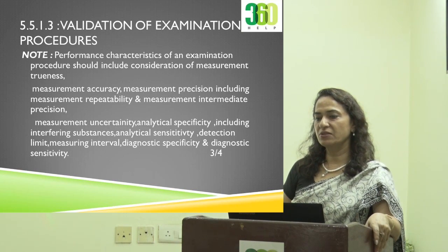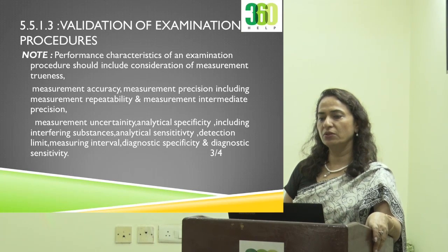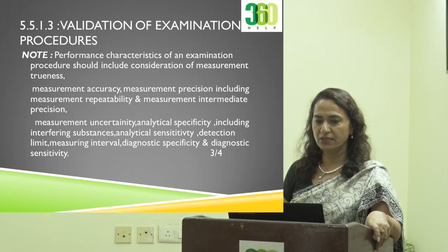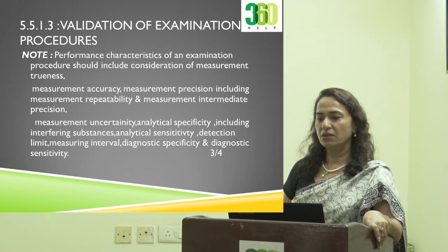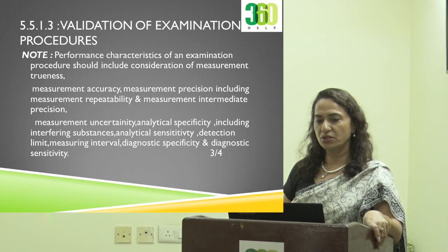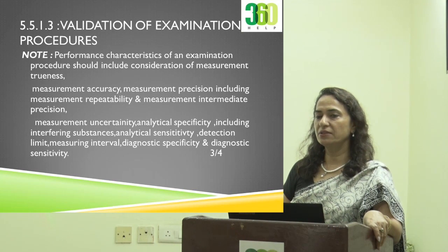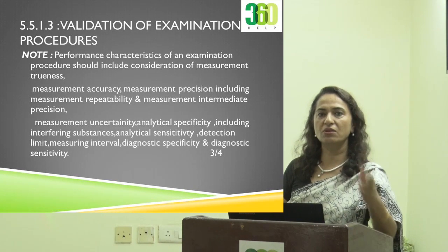Performance characteristics of an examination procedure should include consideration of measurement trueness, measurement accuracy, measurement precision, measurement repeatability, measurement intermediate precision, measurement uncertainty, analytical specificity, including interfering substances, analytical sensitivity, detection limit, measuring interval, diagnostic specificity, diagnostic sensitivity. So it's a long list.